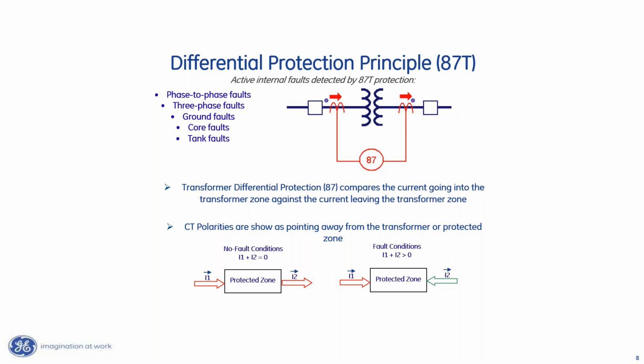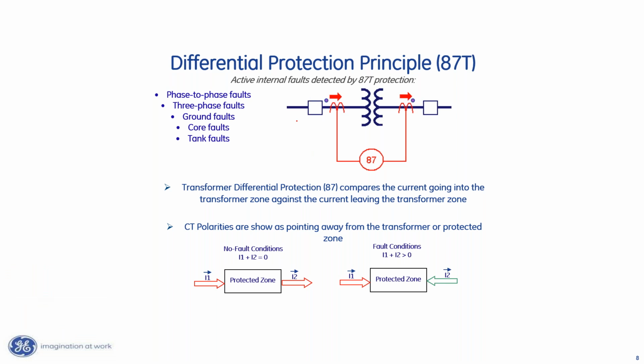So, for example, if I look at this system here, let me get my pen. So I've got current flowing here. That looks like current flowing into the zone of protection. Let's say that's 1 per unit, if it's under normal load conditions, 1 per unit at 0 degrees. And I've got current flowing here, right? So that's current leaving the zone of protection. That looks like 1 per unit at 180 degrees. So those two vectorially sum to 0.